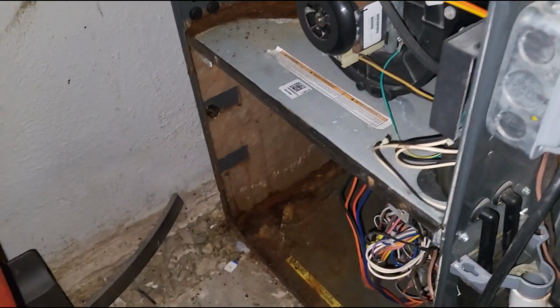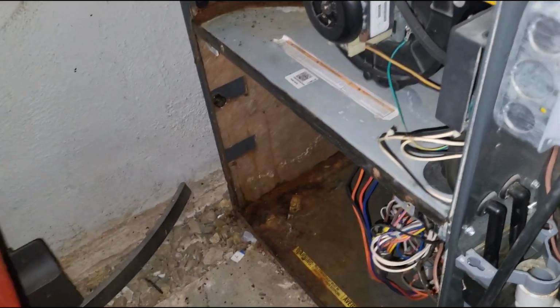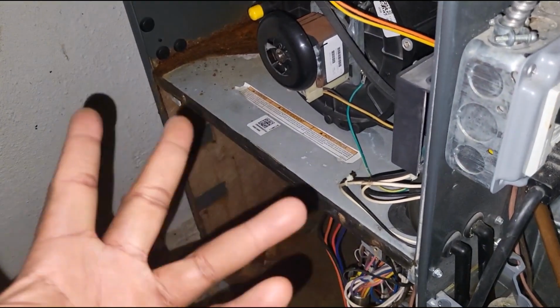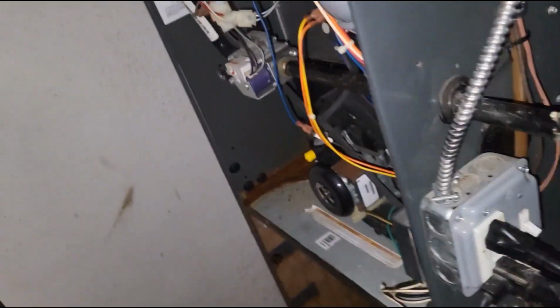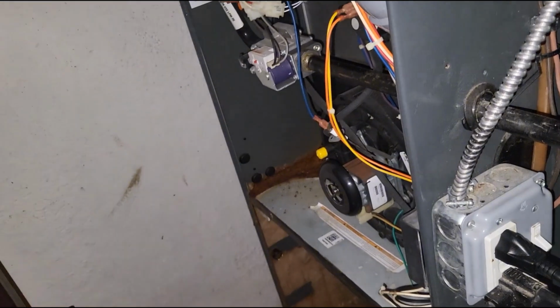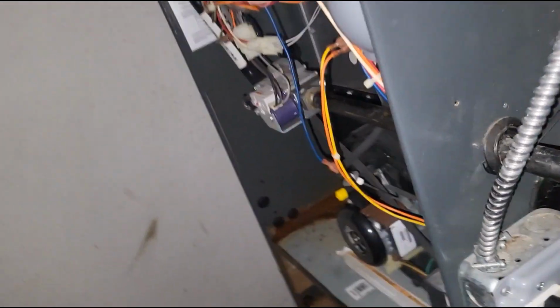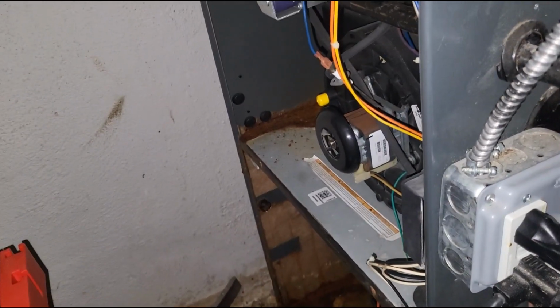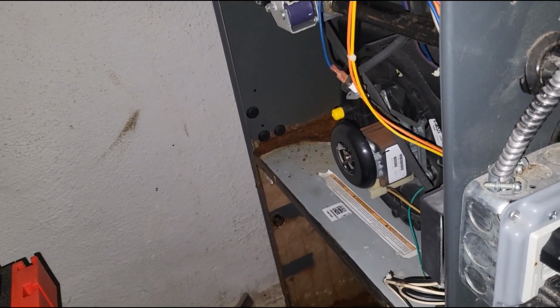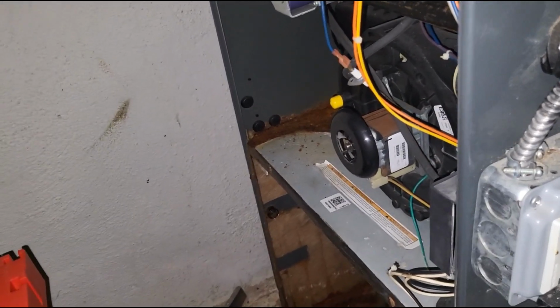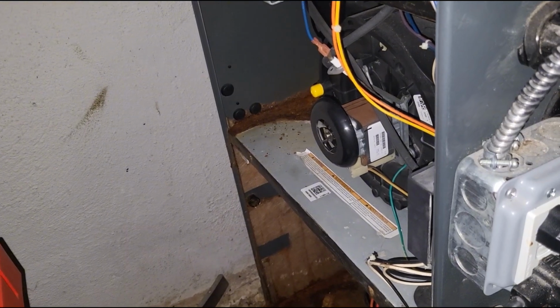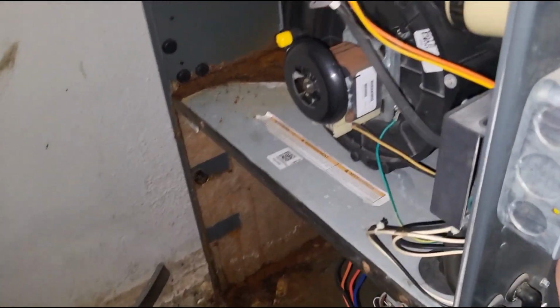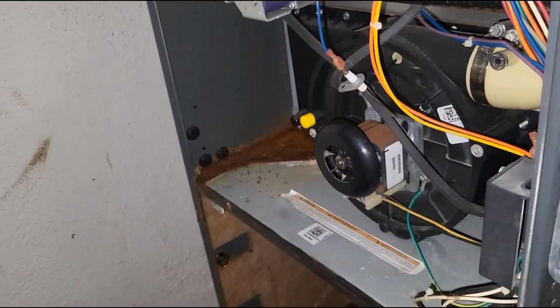Now, once again, that kind of defeats the purpose of having a 2-stage unit, but guys, sometimes people get 2-stage equipment and only want it to operate in 1 stage. So it's cool that you have that feature. So if you do have a 2-stage Goodman unit, you don't have to run new wires, you don't have to have a 2-stage thermostat, you can run everything like normal. But once again, it's best to either have everything single stage or 2-stage.